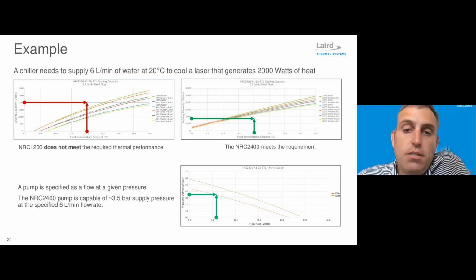In Laird's case, that's the NRC 2400. When we do the same thing here, we see that we're below the performance curves of all the conditions, whether it be a different type of fluid or an ambient condition. So that gives us the correct size refrigeration system. The second part is being able to find a pump that meets that performance. In this case, we needed 6 liters per minute.